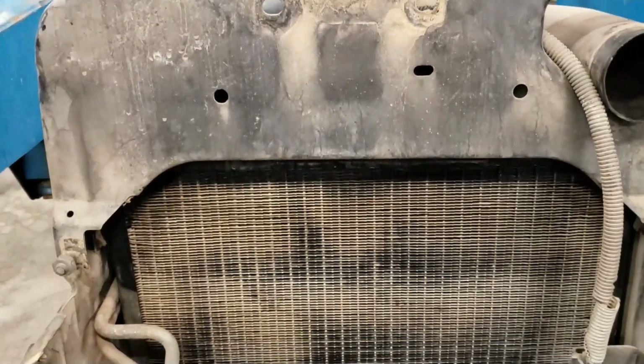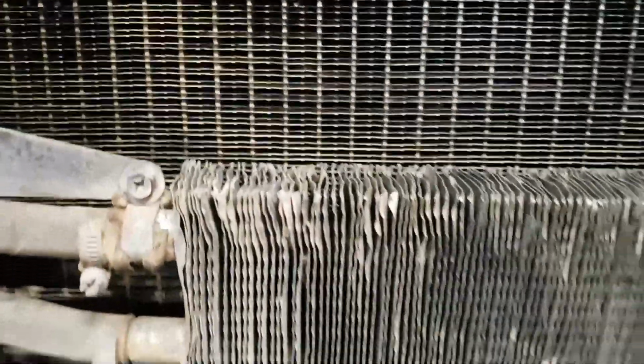I do believe this cleared the problem. Now, I had replaced this radiator. I did not realize it had gotten so dirty. So fortunately now, we've vacuumed out the globs, coagulations of dirt. We have this series of additional coolers here, which I remember now when I was replacing this radiator years ago, thinking, how in the world between these coolers does that radiator get enough air?